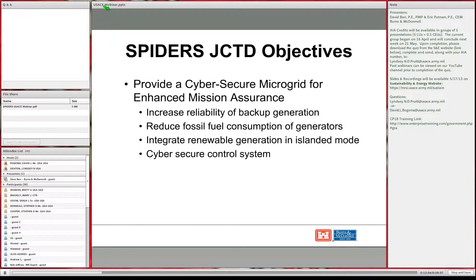The SPIDERS philosophy first decouples generators from their loads. In the current configuration, most facilities have a dedicated generator serving a fixed load through transfer switches. SPIDERS uses the existing distribution system to allow generators to serve not only their current load but also other loads within the distribution network. This provides redundancy—two or three generators operating together—and if one fails, spare capacity remains. It also allows facilities without generators to receive generator power during an extended outage, giving base commanders flexibility to direct power where the mission requires.